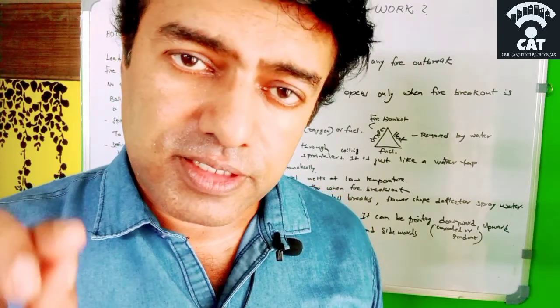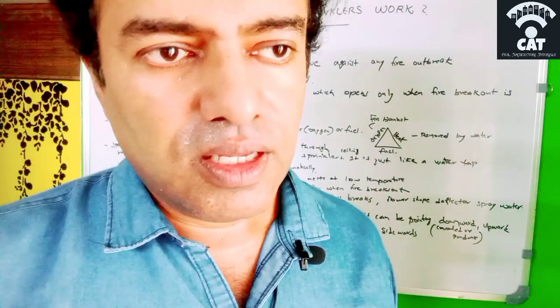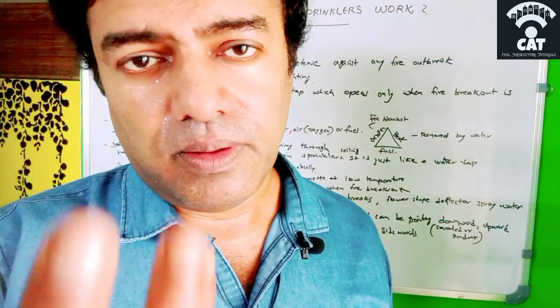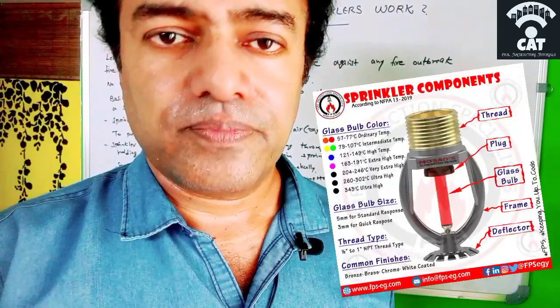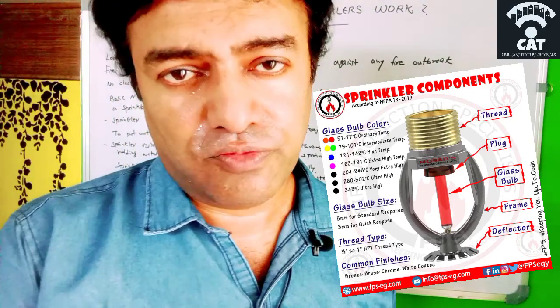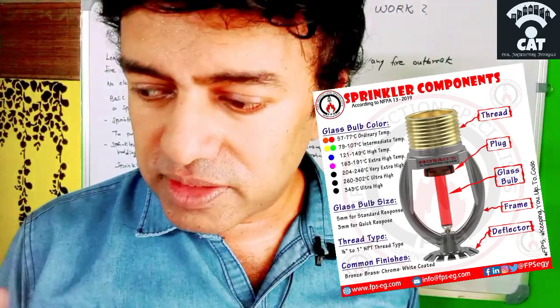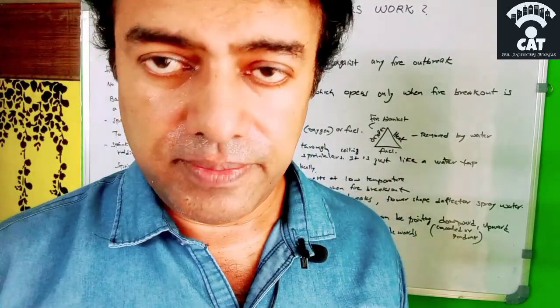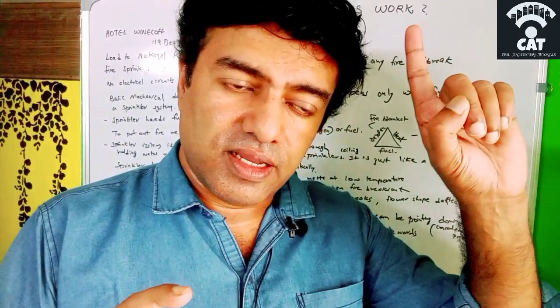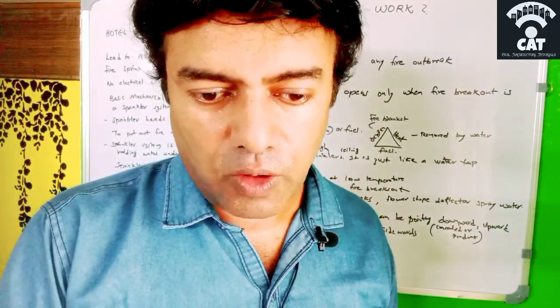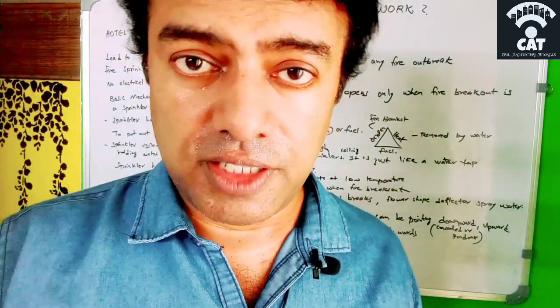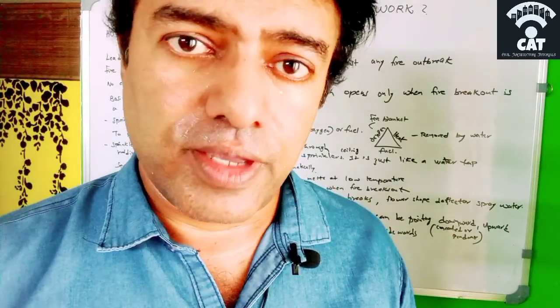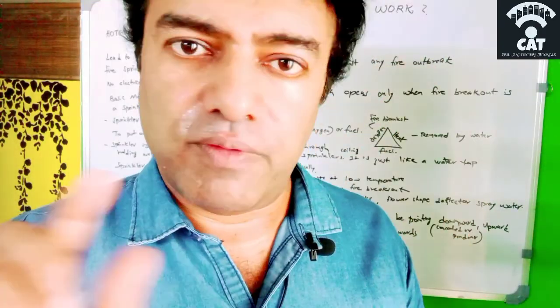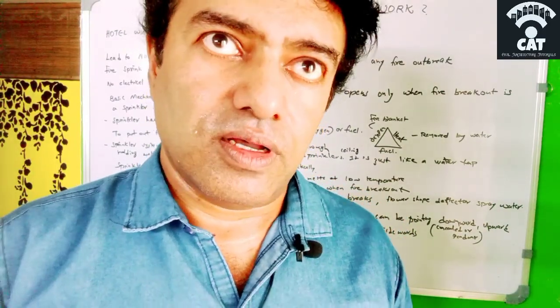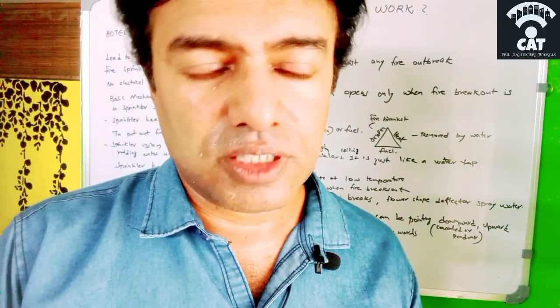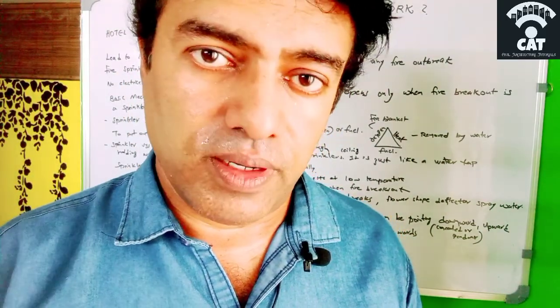So it is supposed to burst at that particular temperature, and then it opens the highly pressurized water in it, which gushes out to a flower-like part called a diverter, and it diverts the water in a circular way so that the radius covers the fire area. If there is a sprinkler at a particular area and a fire breaks out just beneath it, the hot air will first come in touch with that sprinkler only, and not with the other sprinklers. But in many movies, like Hollow Man, you can see the sprinklers opening one by one. It's not like that. It will never happen in real life, because all the sprinklers act individually. All the sprinklers will not open at the same time. They act only individually.